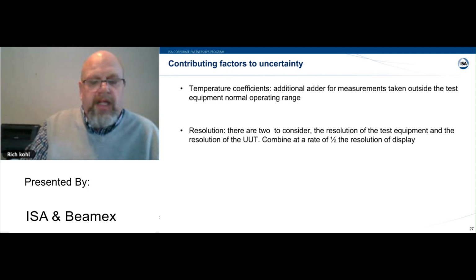So when is this going to apply? It could be cold outside, like it is where Roy is right now, or it could be hot up on the roof in the summer where you might have to take measurements, or up in the ceiling of some factories. It also could be hot near some of the equipment. Maybe you're in a heat treat factory working near furnaces, checking the temperature sensors on that furnace. They generate a lot of heat, so you have to take measurements of your ambient conditions to make sure you're within the operating range of the test equipment. Otherwise, you'll have additional adders that have to be put into your calculation.